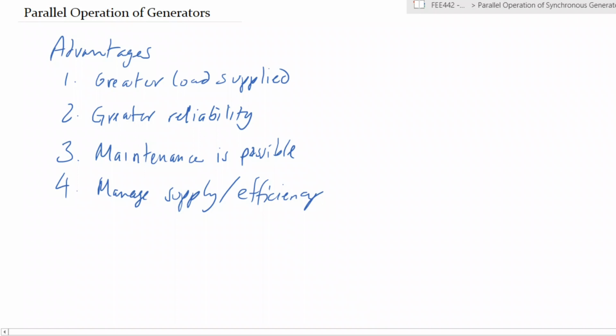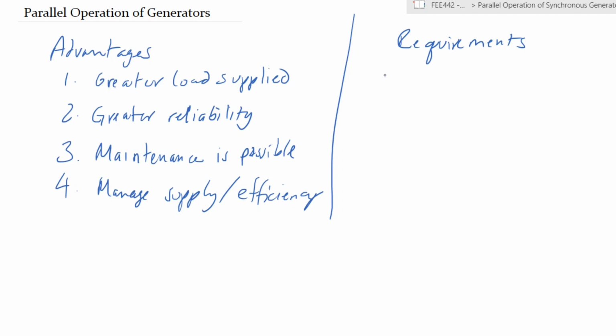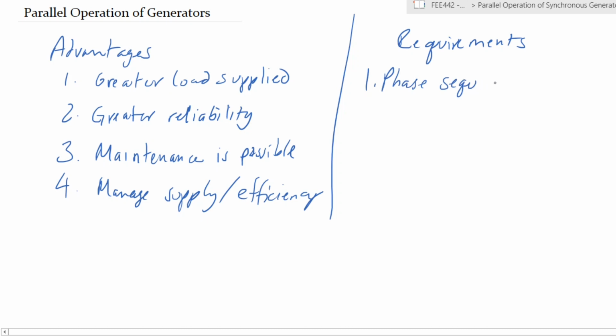So what are the requirements in order to connect generators in parallel? There are a number of requirements in order to have your generators running together, connected to the same load in parallel with each other. So firstly, the phase sequence must be the same.